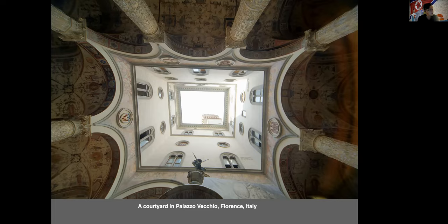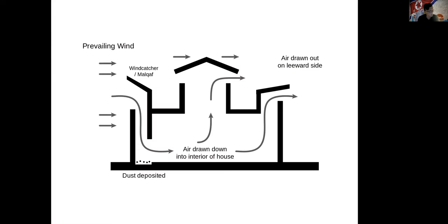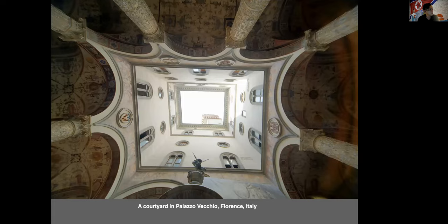And the reason for this is that, just like the previous image, where I showed how the air comes into the building and is funneled out at the tower at the very center and top of the house, the same system is used here. In this case, the courtyard is used to draw the air from outside on the ground floor. And then the hot air that rises higher is pulled out at the very top of this opening that looks like a tower with other upper floors facing it.